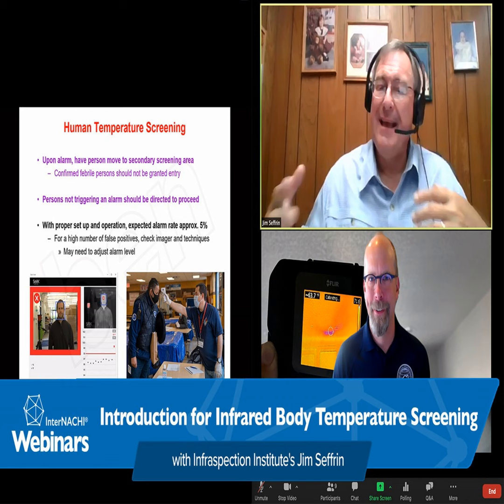A second way to perform infrared body temperature screening is to utilize a purpose-built imaging radiometer. These are typically fixed mount, non-portable systems intended for human temperature screening. They're purpose-built instruments. A third way, and this is where home inspectors come into play, you can use a commercial grade imaging radiometer. These are typically portable handheld systems intended initially for commercial and industrial use. Provided they meet certain protocols, they can be used for elevated body temperature screening.